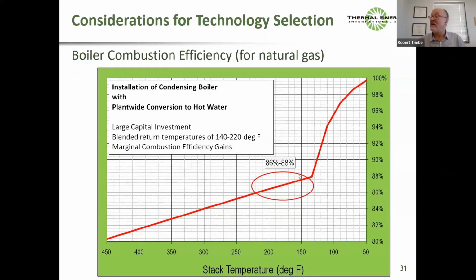So let's just say we're coming back, I'm going to go in the middle here, 175. So that circuit from the plant's coming back to the boiler, to the water heater at 175. If it's coming back at 175, I can only cool the exhaust to maybe 190. If I can only cool the exhaust to 190, this is where my efficiency is. So that's great. That's wonderful. I've put in a condensing boiler. I'm not cooling it down to the dew point, so I'm not putting in a direct contact system. It's not cold enough for me to put in a direct contact system. I put in an indirect condensing boiler or a traditional boiler and an economizer, and I bring all of that hot water back and I run 86 to 88% efficiency.